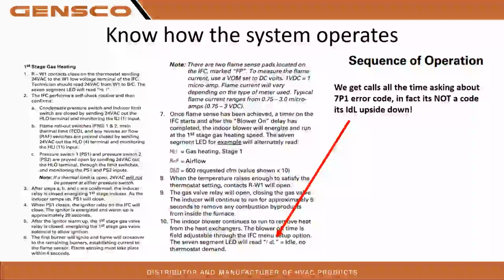I put this in there because we get this call quite a bit on this IDL, which is idle, so it means the system's just sitting there waiting for a call. We get the call all the time: what's the 7P1 error code? It's not listed. It's not a code. It's just IDL upside down. So keep that in mind when you and your technicians are looking at a job, or a homeowner snaps a picture and texts it to you saying there's some kind of code on the furnace. You can tell them that's just a standard waiting call. It's just idle. It's a call we get regularly enough, so I figured I'd throw that in there.